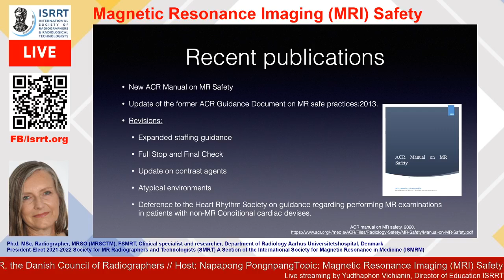So looking into the revisions with regard to expanding staffing guidance, it states that there will be a minimum of 2 MR technologists, or 1 MR technologist and 1 other individual with the designation of MR personnel, in the immediate zone 2 through 4 MR environment whenever patients are in the environment. And during this time, the 2 MR personnel must be able to directly communicate within earshot of each other at all times.